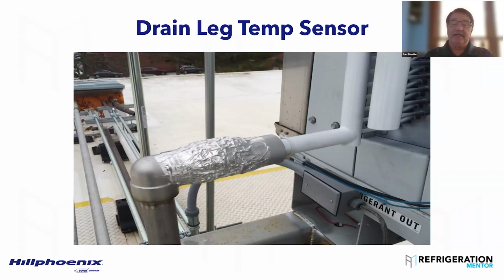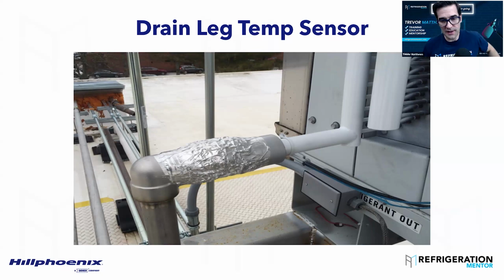In this case, I would have chosen the white pipe because it's thinner and heat transfer is quicker. The way this was mounted is going to cause a lag in our temperature reading, because now we're heating up all that stainless steel pipe. Yeah, exactly. So that's a good point. Location is very, very key.